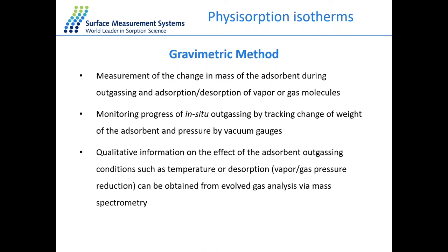The gravimetric method allows you to see whether the material is completely dry or not. We can also collect additional qualitative information during the outgassing of the adsorbent using temperature, by performing desorption measurements and coupling the gravimetric system with mass spectrometry in order to analyze evolved gas.